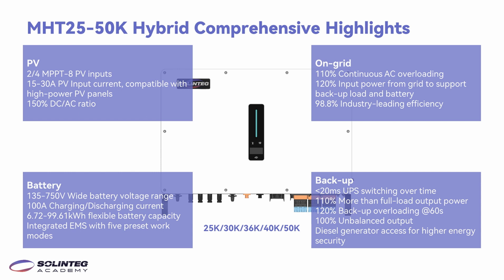On the battery side, the battery voltage range is very wide, 135 to 750 volts, so it covers a wide niche of customers' configuration. The charging and discharging current is 100 ampere, so it can fully charge a C&I battery in a short time and have a large discharging power, enabling connection of big power backup loads. If you choose the Solinteg C&I battery, the battery capacity is 6 to 100 kilowatt hours. Also, the inverter is integrated with EMS with 5 preset work modes. So you can set different work modes according to your different requirements.